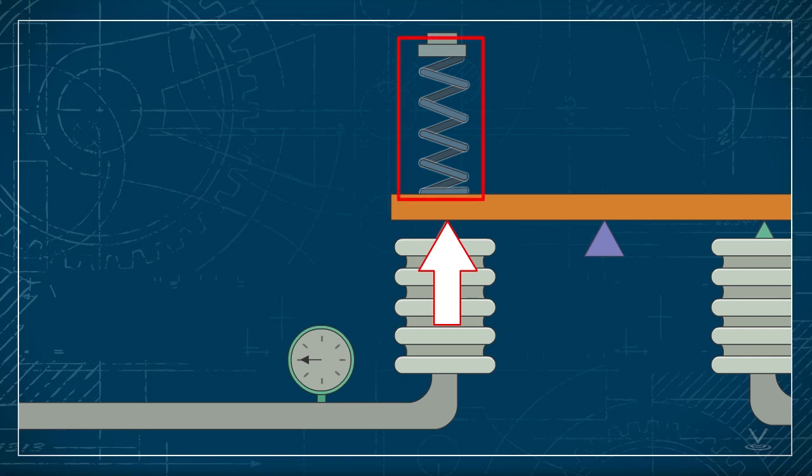The setpoint for this controller is established by the tension of a spring, which opposes the force of the input bellows. When the process variable is at setpoint, the two forces are balanced and the beam is stationary.